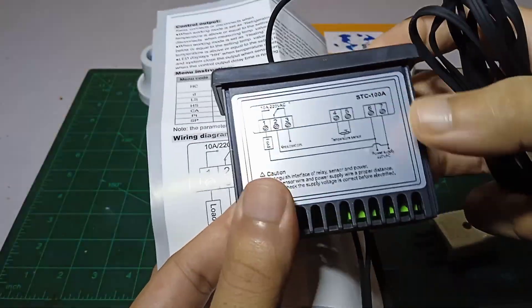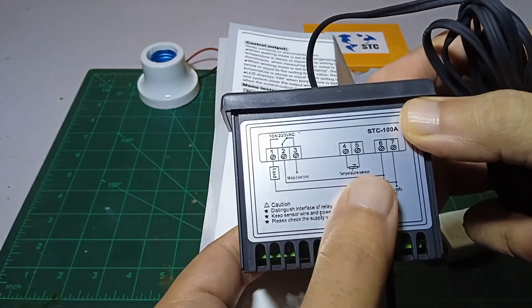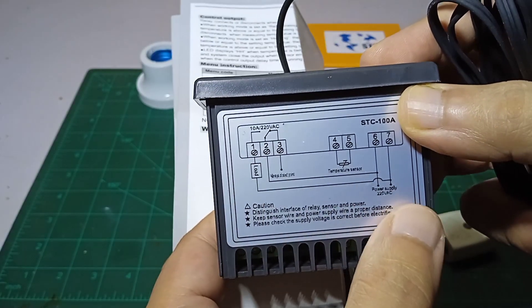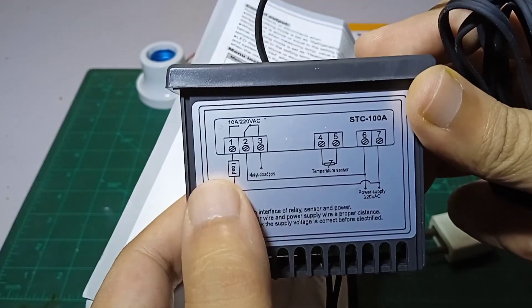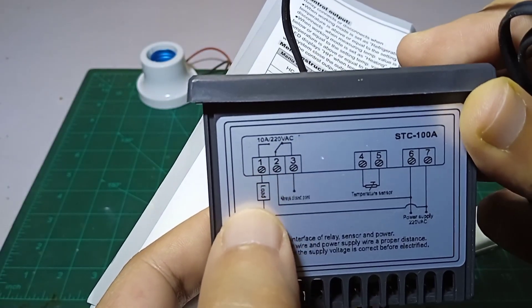The wiring is easy according to the diagram. We have to connect the temperature sensor on pins 4 and 5, which I have connected. Then we have to give 220V power on pins 6 and 7. From here, it is showing the neutral wire should be going directly into pin 2, and the load — like a heater — has to be connected on pin 7 as well.